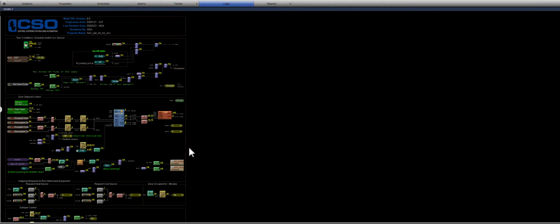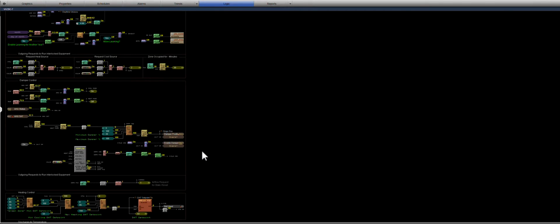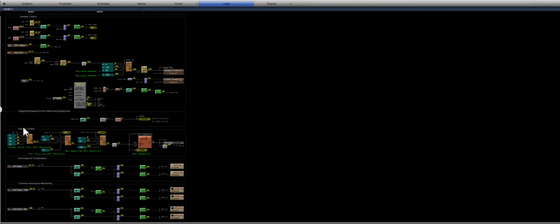I'm not sure why this database error is persistent. I found this in some areas and some not. The way I've been able to verify that is going to the logic and scrolling down to the heating section, the hot water valve heating control here in this section, and seeing our output going to a point called "not used." So it's incorrectly tagged in the system as the hot water valve.